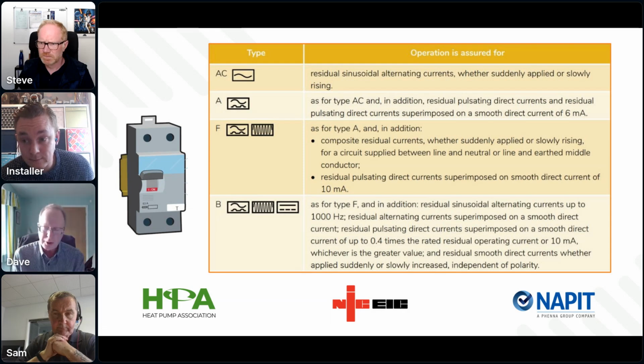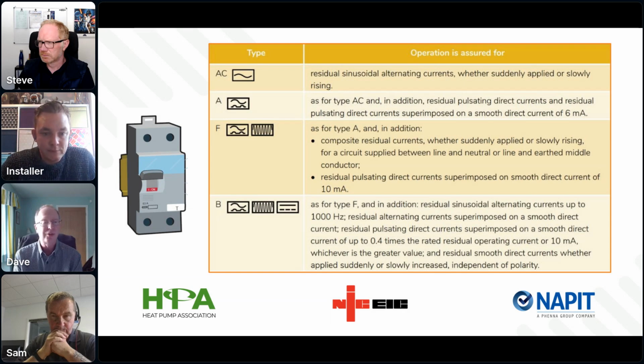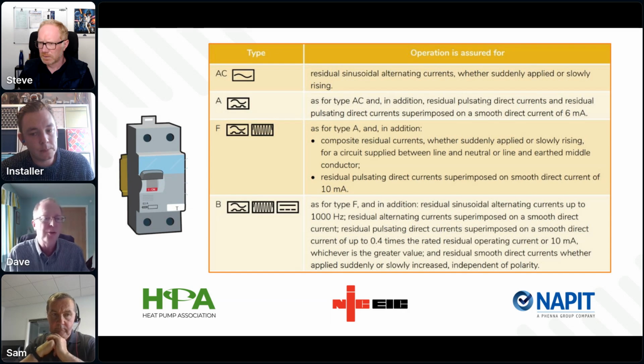Going back to the question about when there is nothing to support a choice. Now, hopefully that shouldn't be the case. We put together the steps of guidance specifically in order to find the answer to the question about what RCD you should fit. And therefore it should be a very unusual situation that brings you back to the point where there is no advice at all. But let's assume theoretically that is the case. We know that Type As often cannot reliably detect faults with the kind of frequencies and DC components that we've talked about where there are inverters. So if I had nothing else to go on, I would probably rule out Type A.